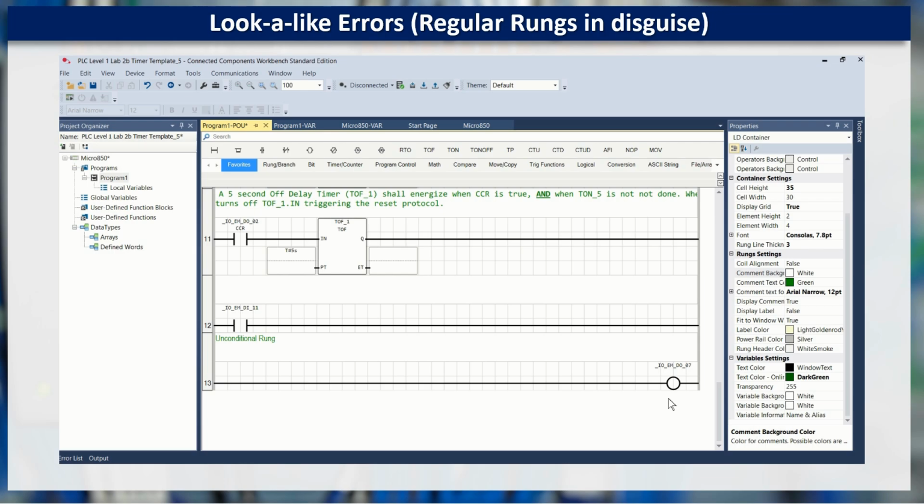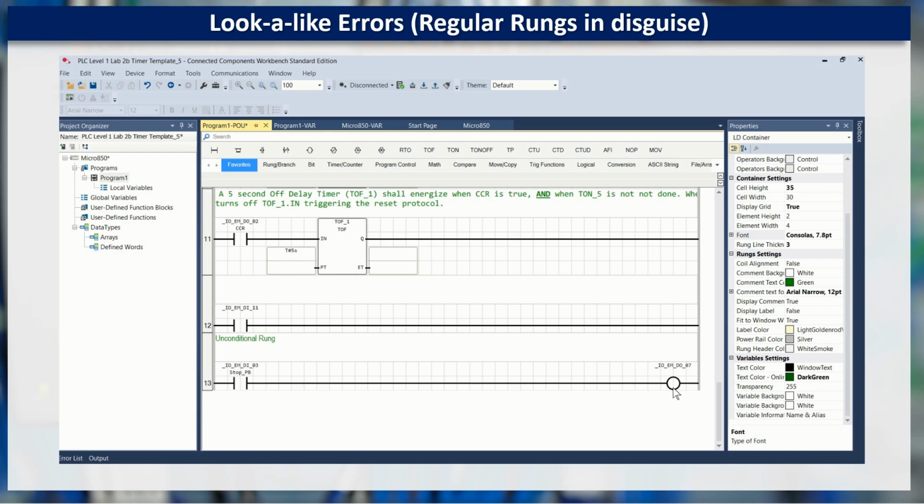It has very specific functions, but make sure when you're putting an output that you have a way to turn it off. So in this case here, we would definitely want to have our digital input stop button. So at least pushing the button is going to turn it off. The rung above it, I have an input and I have no output. Now, the software will actually let you do this, and it'll actually let you download it to the Connected Components Workbench. But that happens to be a feature of this particular processor, this particular software.